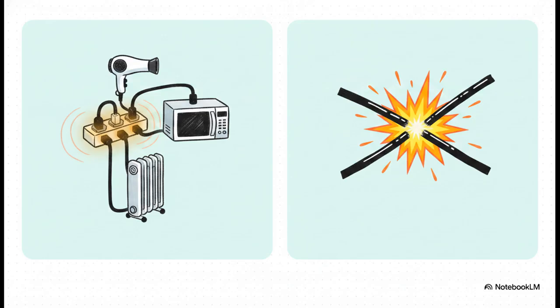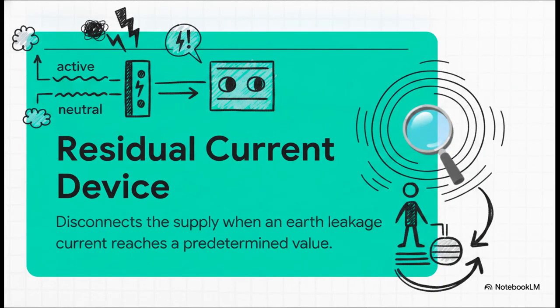But on the right, we have the short circuit current. This is a sudden, explosive, violent fault happening directly between conductors. It's over in milliseconds. Our electrical guards, the circuit breakers and fuses, have to be perfectly coordinated to detect and defeat both the slow burn and the violent explosion. But here's the catch. Circuit breakers aren't actually enough to protect humans from a shock.